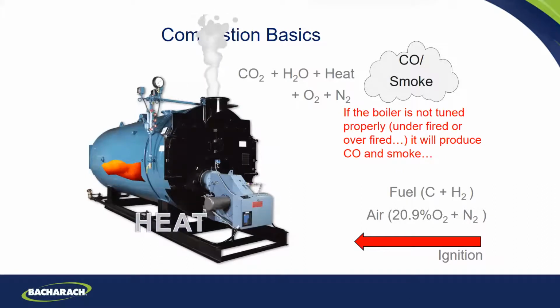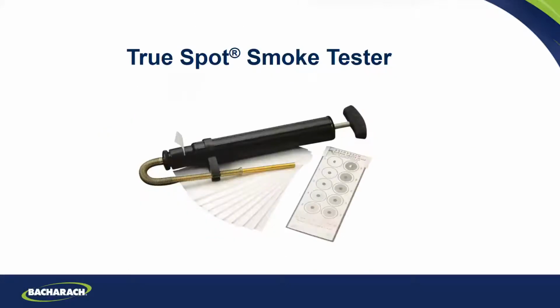And then if you're in oil and you're up in northeastern North America, both Canada and New England, you may make smoke in your process. So we do have a product for that. If you're doing oil and you're going to take a combustion test, you always want to take a smoke test first, because you don't want to run that soot through your boiler or furnace.